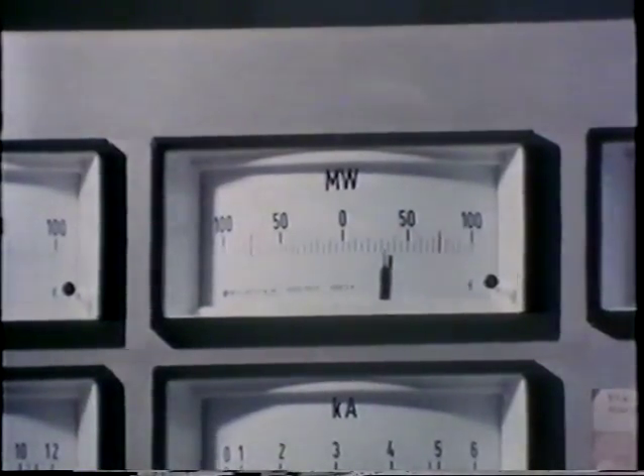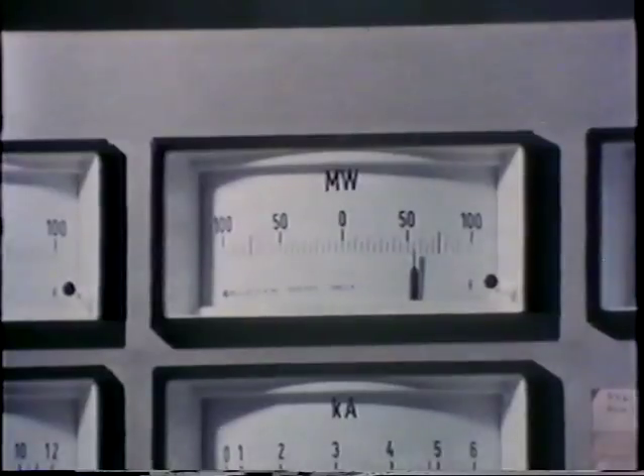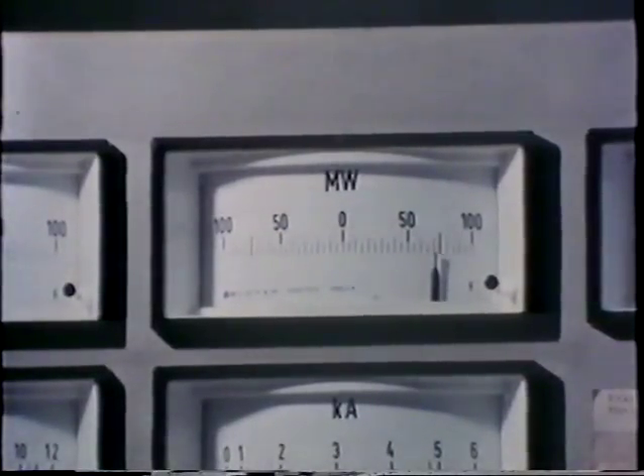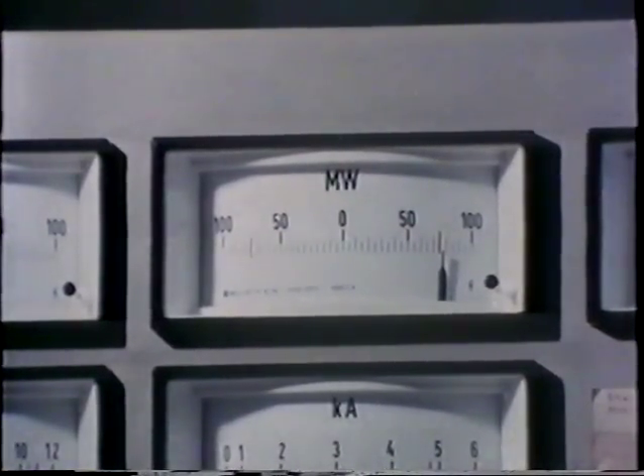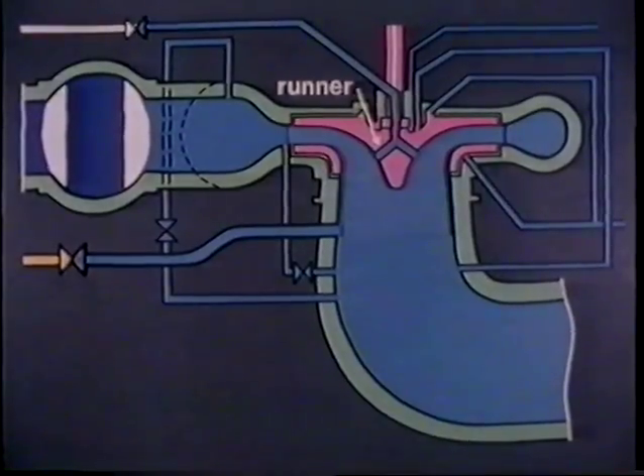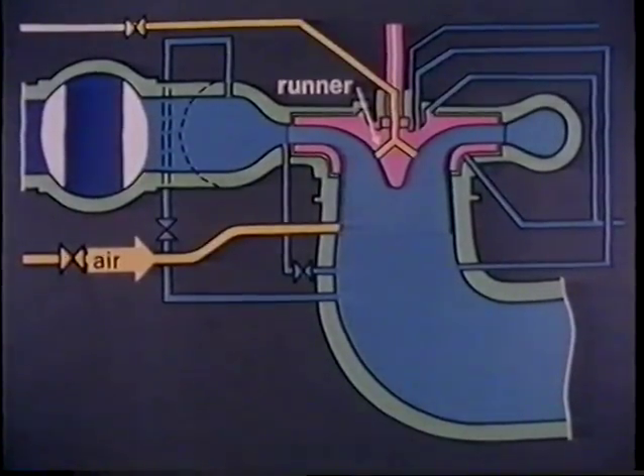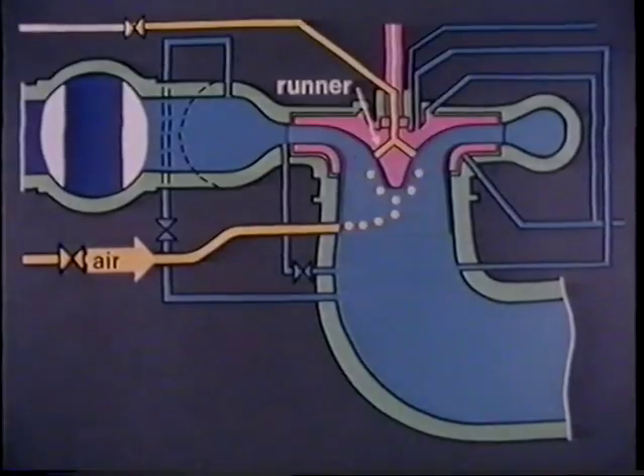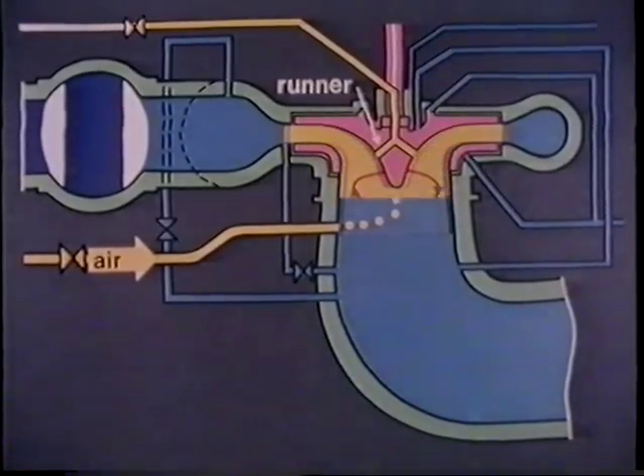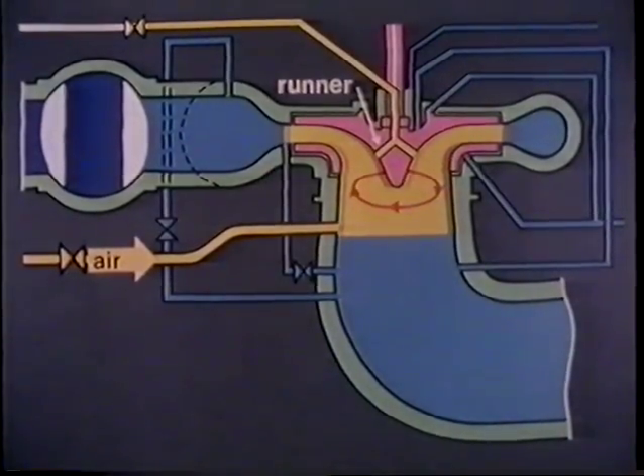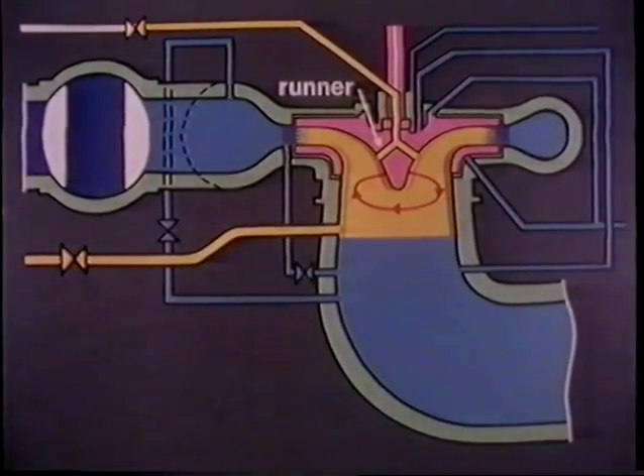Thermal plant requires 3 to 4 hours for starting up, compared with 70 seconds for the Turlough Hill machines. In the pump startup sequence, compressed air is used to depress the water below the level of the runner. The pony motor then comes into operation, bringing the main machine from standstill up to rated speed in 3 minutes. The driving torque of the pony motor remains constant up to about 90% speed.